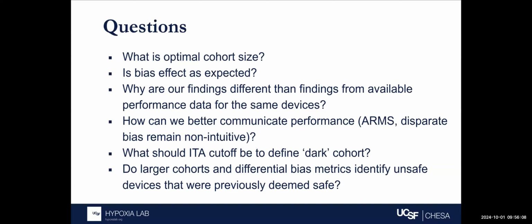Hey, Kumo. Great question. So we, irrespective of the 510K pathway, for any new pulse oximeter, so significant changes in the electro-optical pathway or algorithm that classifies it as new, would be asked for clinical data, controlled desaturation lab data, to meet the performance requirements or recommendations in our 2013 guidance. Hope that answers the question, Bev. Thanks, Kumo. Yeah, thanks. Sorry, I was muted. Thank you. That's helpful.